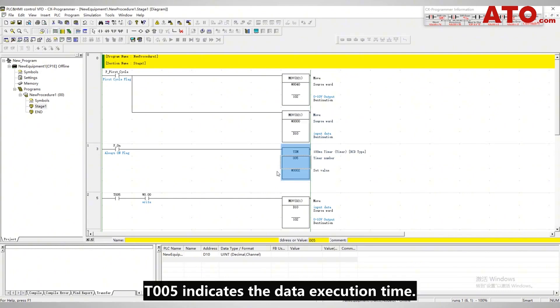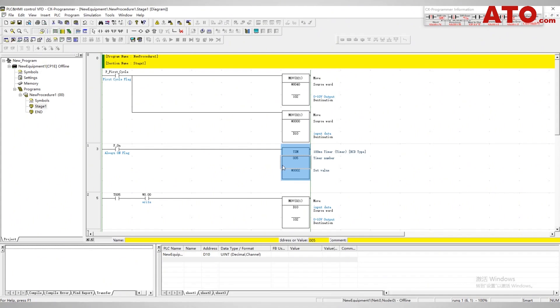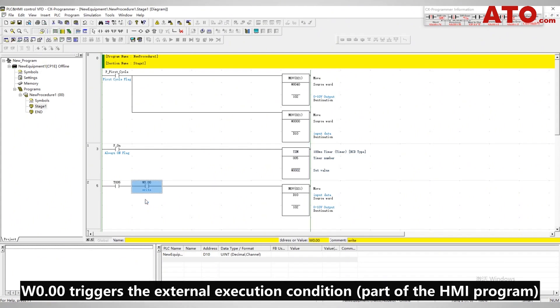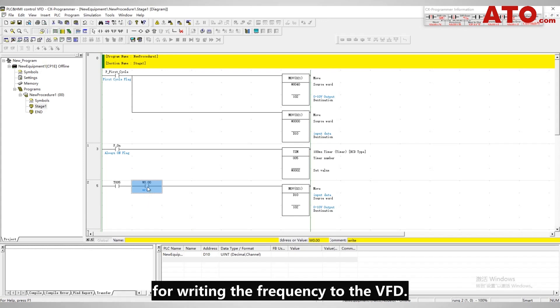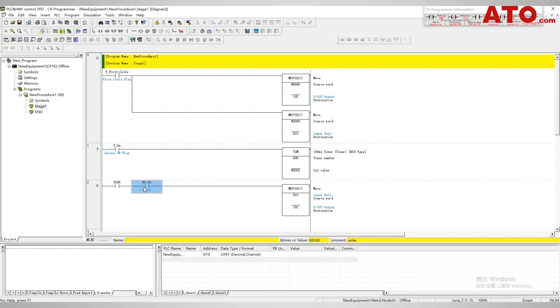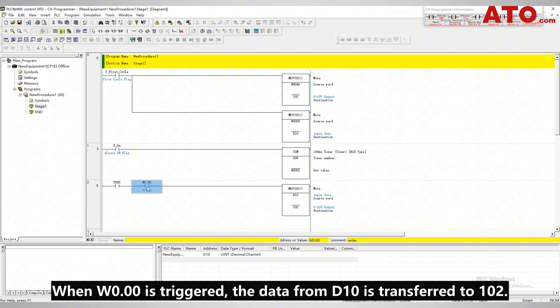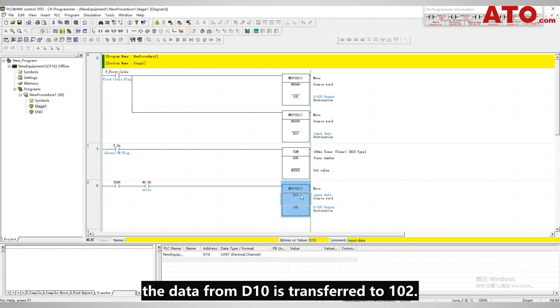T005 indicates the data execution time. W0.00 triggers the external execution condition, part of the HMI program, for writing the frequency to the VFD. When W0.00 is triggered, the data from D10 is transferred to register 102.